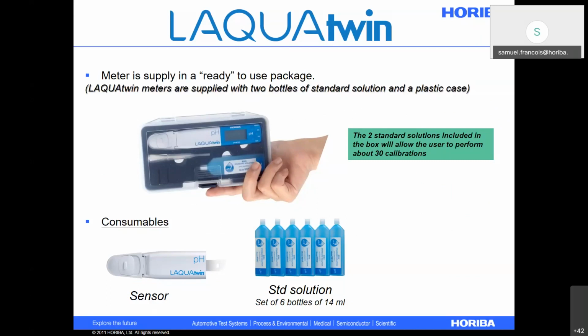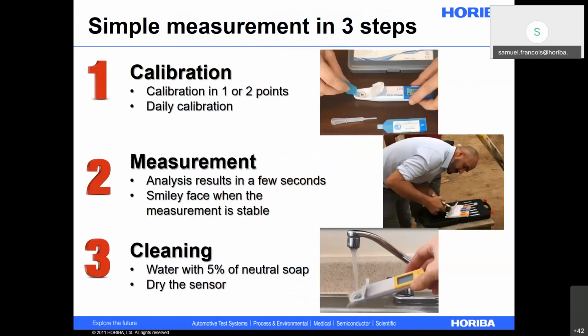The lifetime depends on the frequency of use and also the type of sample. Sorry. So, the way to use the measurement: we have 3 main steps. First is the calibration. We can do the calibration in 1 or 2 points, as a daily calibration. Second, we do the measurement. The result appears in seconds, and when the measurement is stable, we have the smiley face. Then finally, we want to do the cleaning. We can use water with 5% neutral soap if the sample is kind of dirty, and then we can dry the sensor.